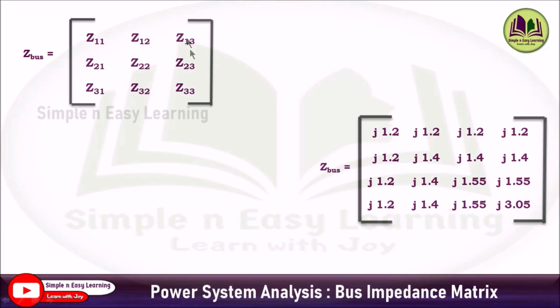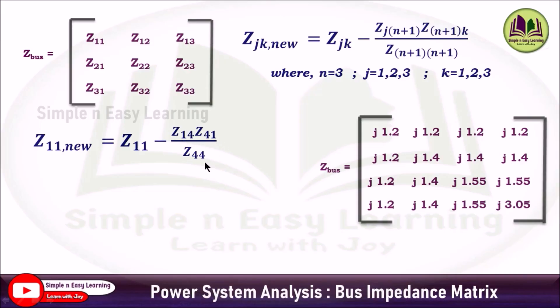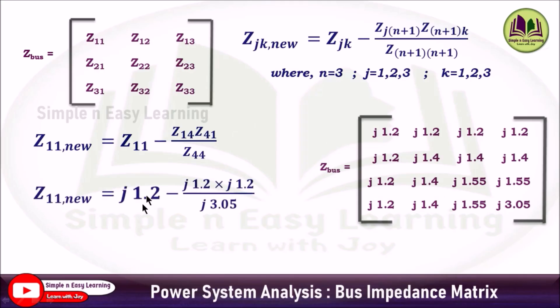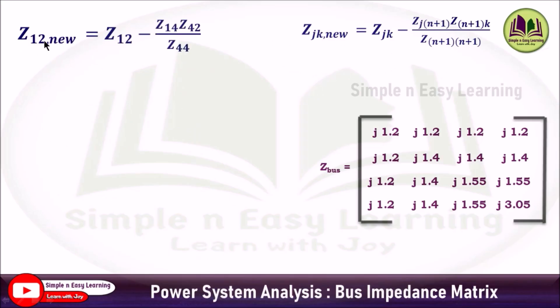We need to obtain nine terms. First, Z11: with j=1, k=1, the formula gives Z11(new) = Z11 − (Z14 × Z41) / Z44. Substituting from the matrix: Z11 = j1.2, Z14 = j1.2, Z41 = j1.2, Z44 = j3.05. So Z11(new) = j0.728.